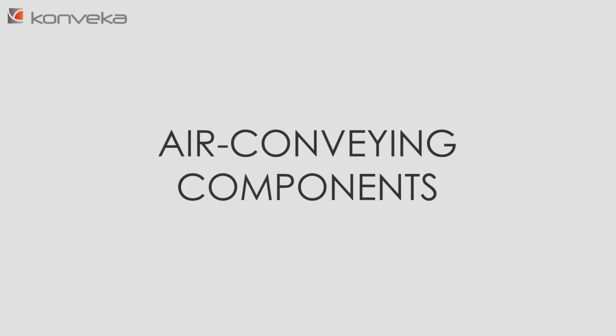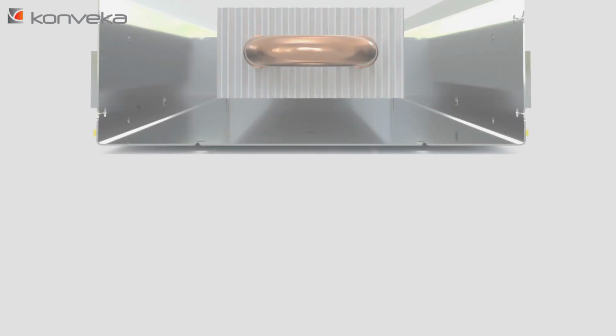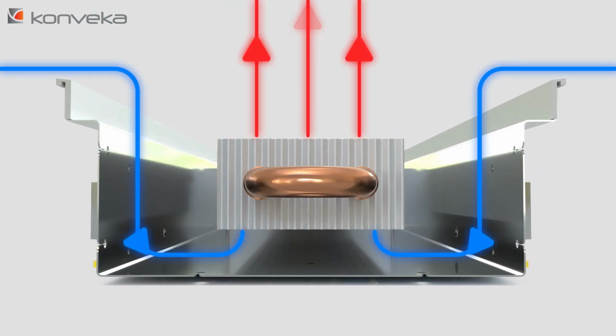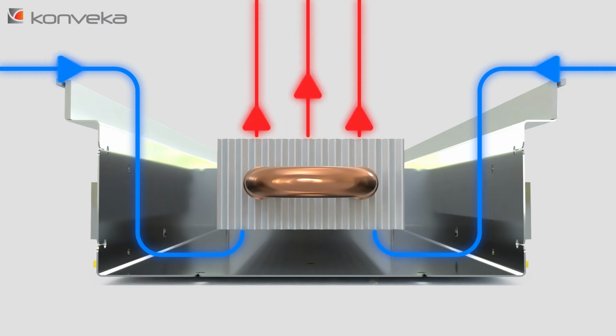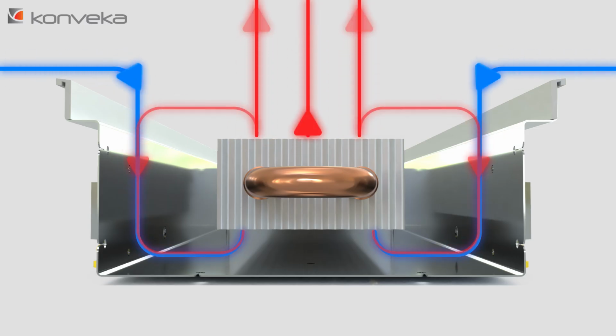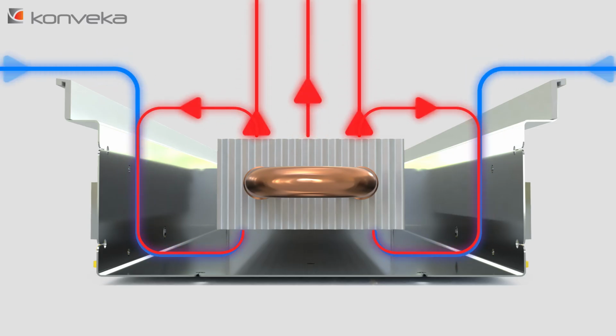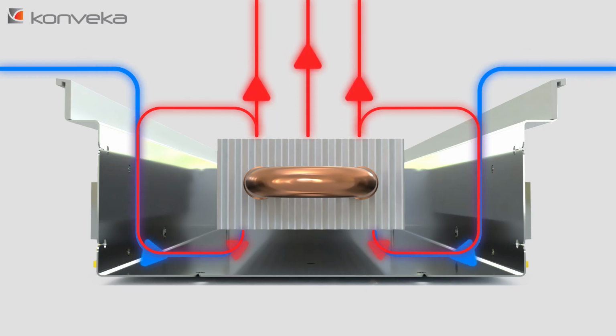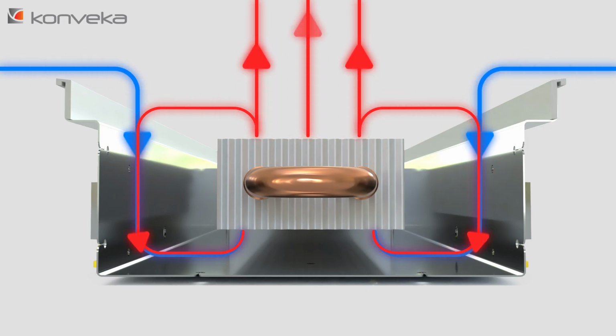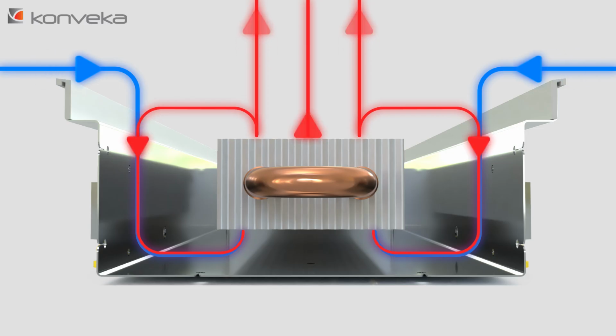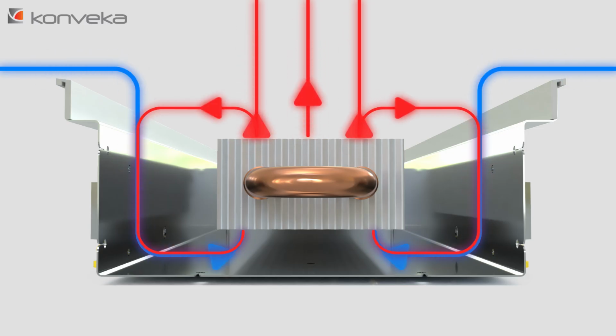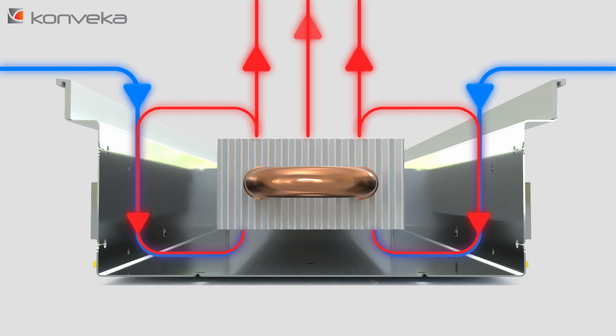Air conveying components. The design of trench convectors with natural convection must ensure the smooth circulation of cool and heated air. Laboratory tests revealed that the cool air, as it moves under the heat exchanger, partially mixes with the heated air. In this way, part of the warm air is directed back under the heat exchanger. In other words, part of the airflow recirculates. This reduces the output of the appliance and impairs the smooth rise of warm air in an upwards direction.